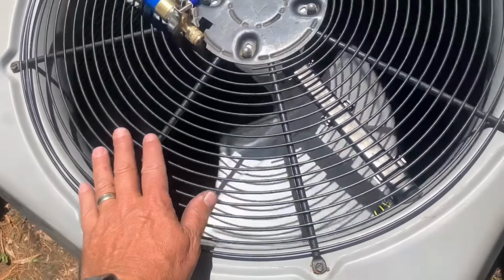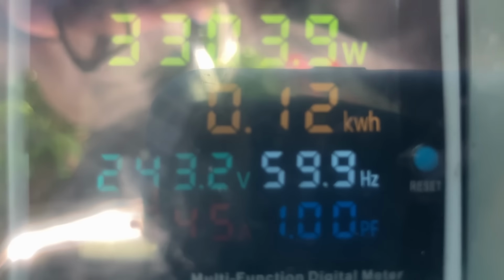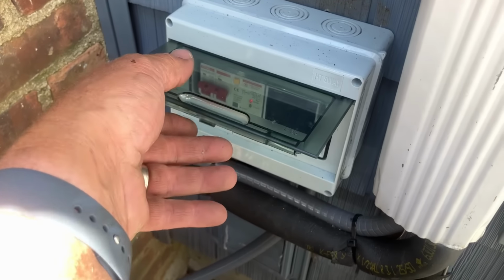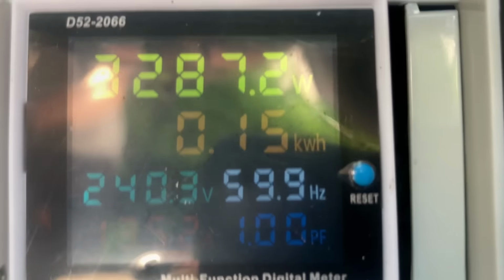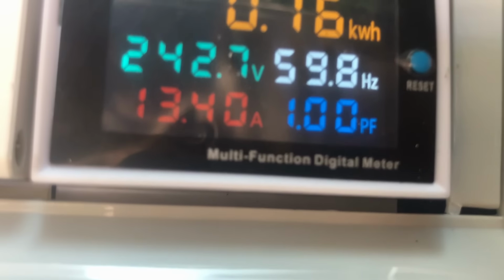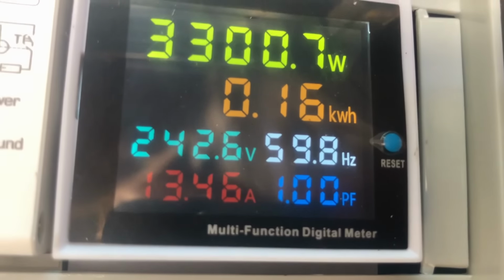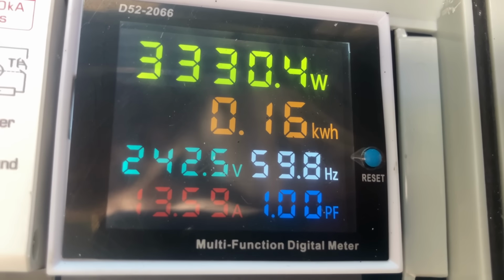That wasn't me. I just had a call. Cooling is off. So, let's see. We're at 3,289 watts. 0.3 kilowatt hours. Right? We have 243 volts. Almost 60 hertz. 13.33 amps of power. Let's get a better view of that. The sun does not cooperate. There you go. 13.4 amps. 242 volts. There's all the info right here.